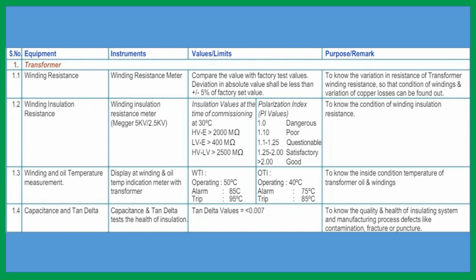Then insulation resistance, I have already told you the IR value. High voltage to earth is 2000 megohm or more. Low voltage to earth, 400 megohm or more. High voltage to low voltage, 2500 megohm or more. And the polarization index, that means R60 by R10 and R600 by R60.